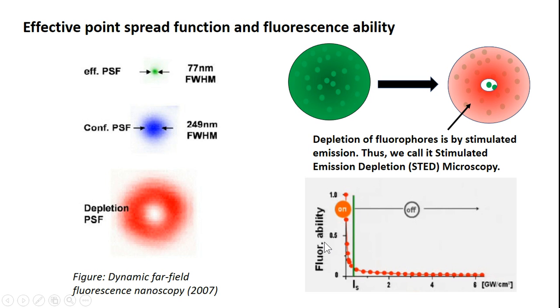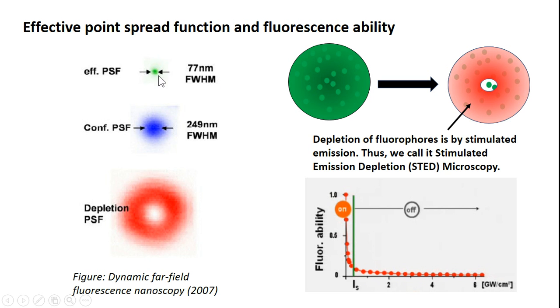STED depletes fluorescence based on a plot of fluorescence ability versus the intensity of the incident beam. Once the intensity of the incident beam is higher than the saturation intensity, the fluorescence ability depletes. The STED beam intensity is always higher than the saturation intensity, which is why it depletes the fluorescence except at the central focal spot, resulting in a very narrow effective point spread function.